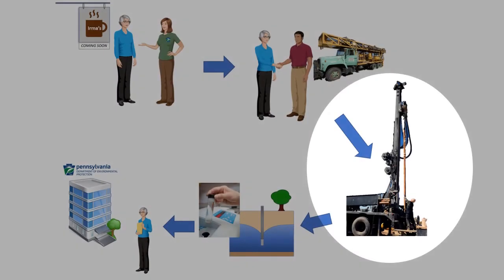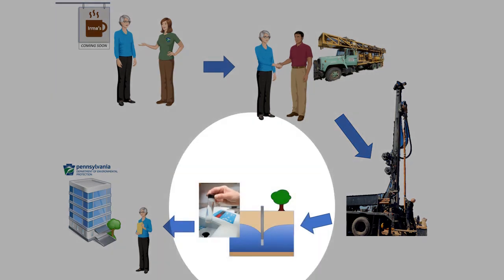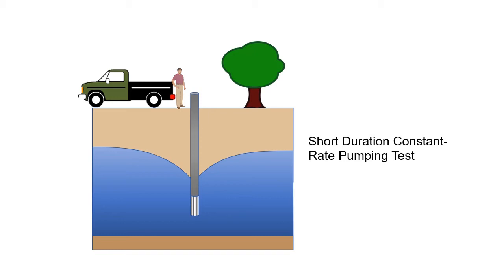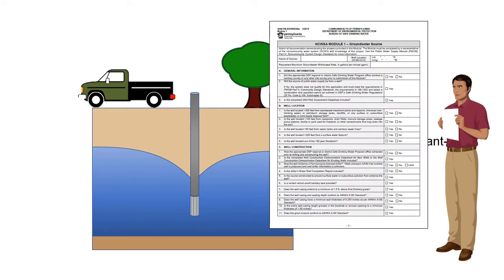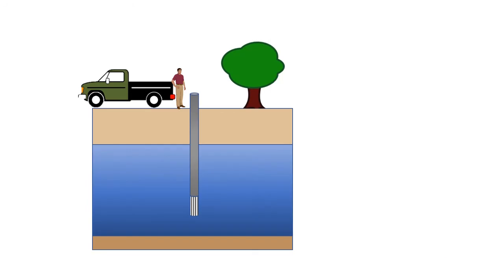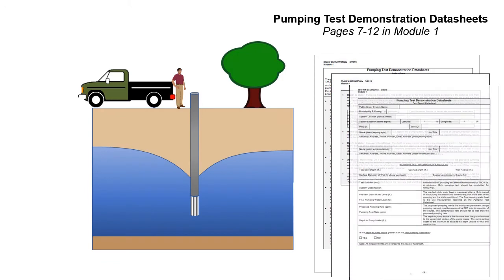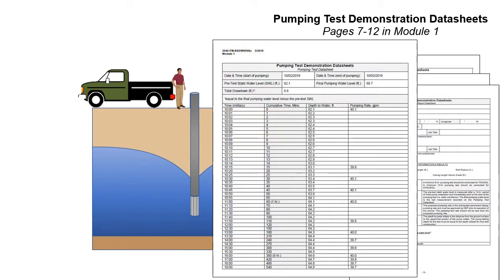After the well is drilled and properly developed, the fourth step is to confirm that the well produces enough water to meet system demand and that the water is of high quality. This is achieved by conducting a short duration constant rate pumping test. Ideally, the pumping test should be conducted by the driller shortly after the well is constructed. The applicant should make sure that their contracted pumping test operator has a copy of Module 1 prior to initiating the pumping test. The pumping test operator should perform the test in accordance with the pumping test demonstration data sheet's instructions and complete the data sheets found in the Module 1 application on pages 7 through 12.